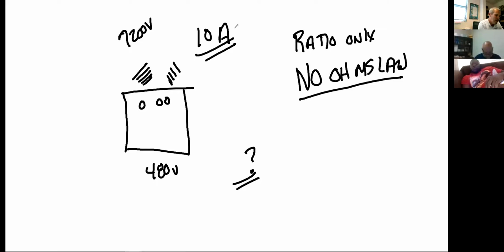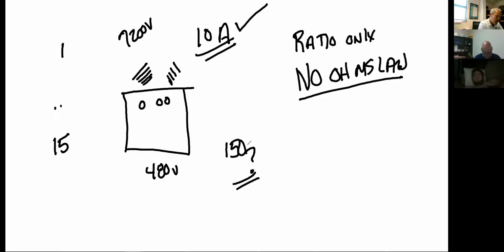Once I have, and it's sitting right here, if I've got 10 amps... let's do this one real quick and we'll take a break. First, what's the ratio? 7,200 divided by 480. I think it's 15 to 1. 15 times 480 is 7,200? Yeah, okay. So 15 to 1, 10 times 15 is what? 150. All right, so that's the first part of the question.